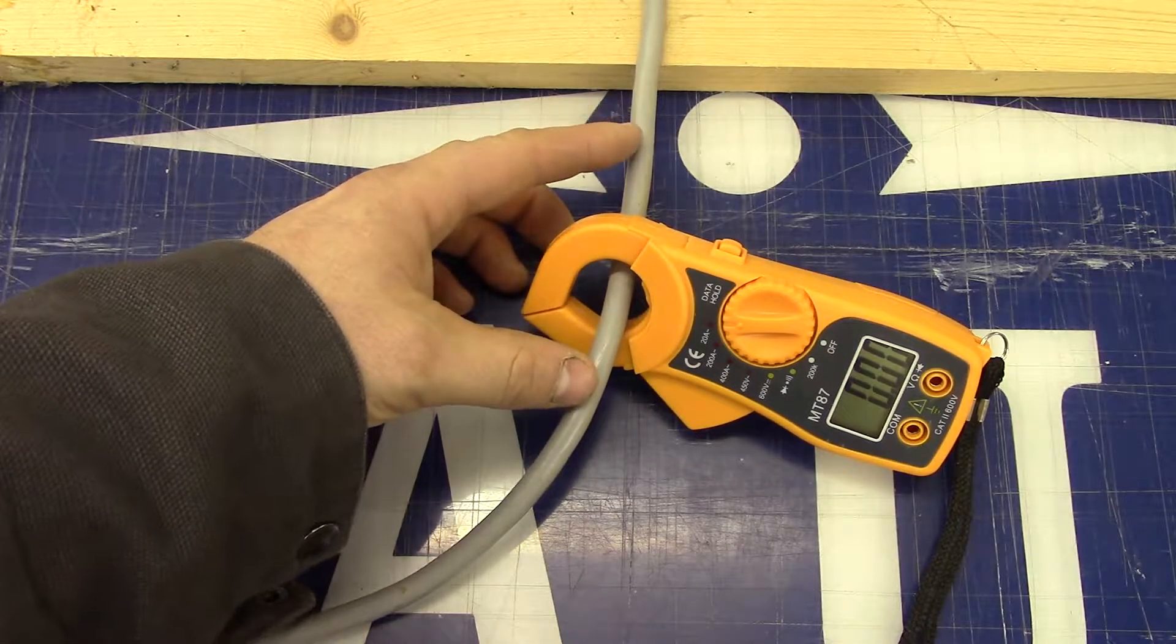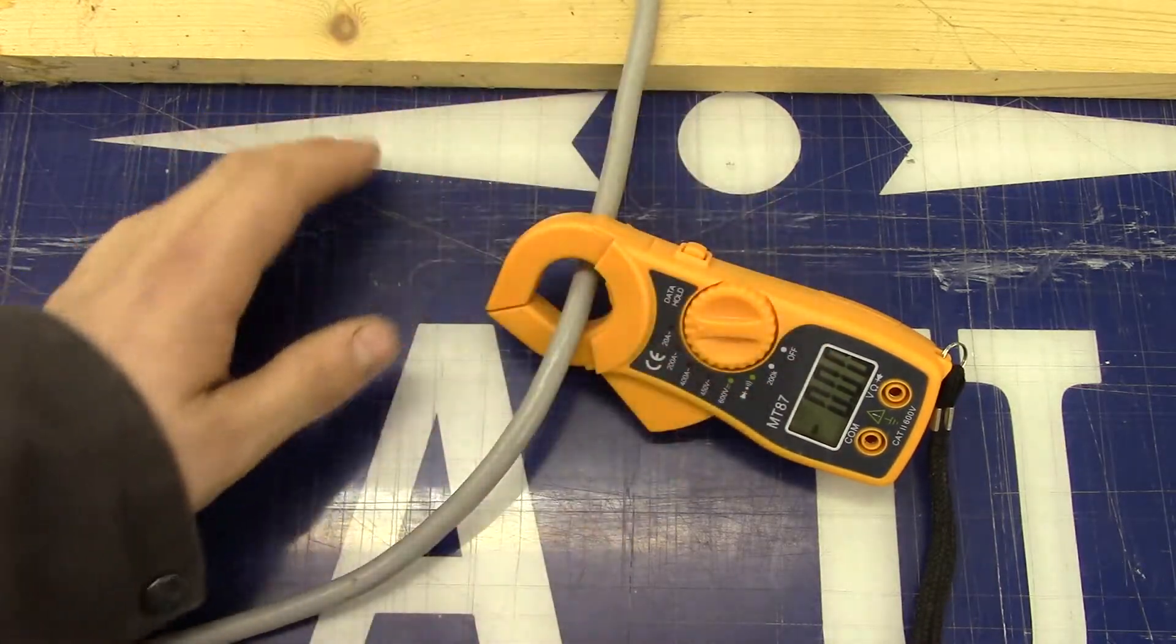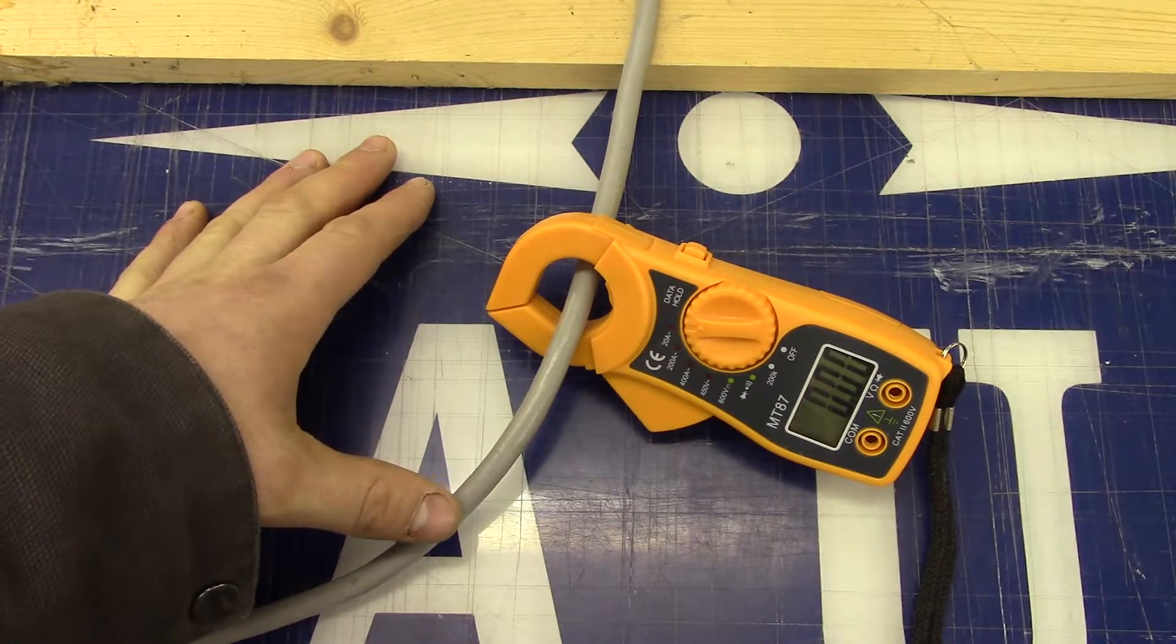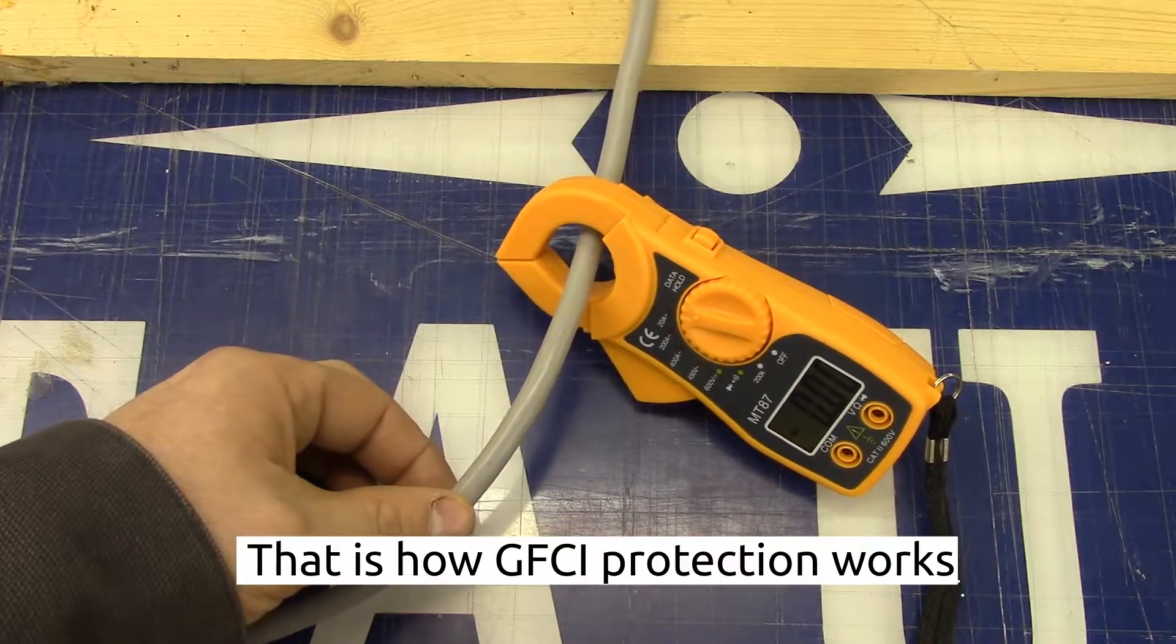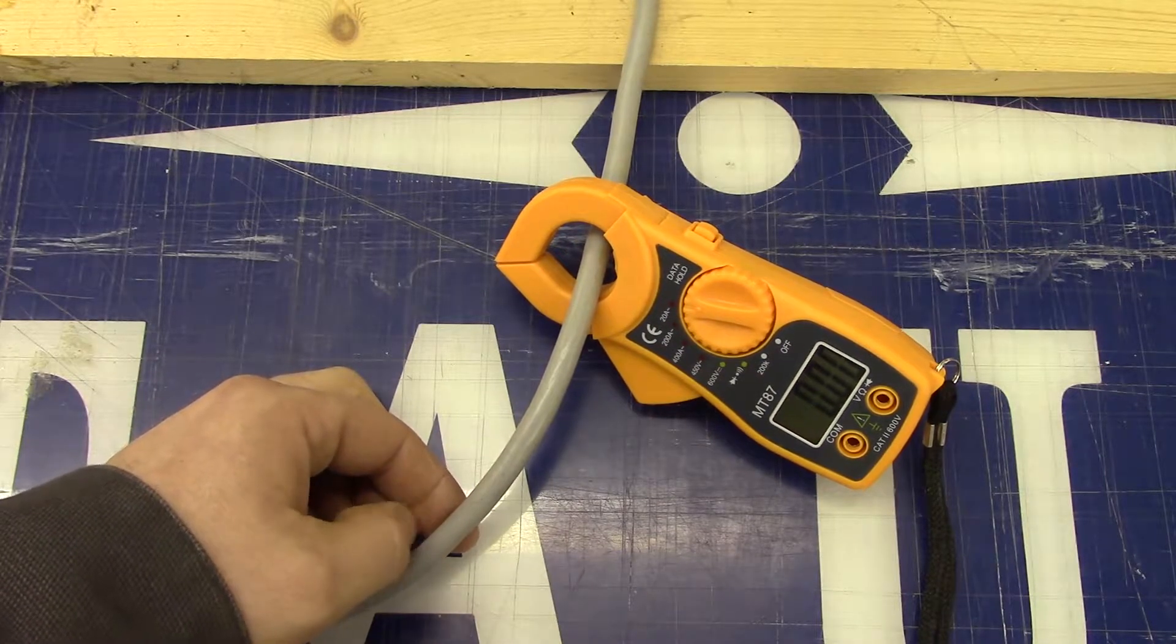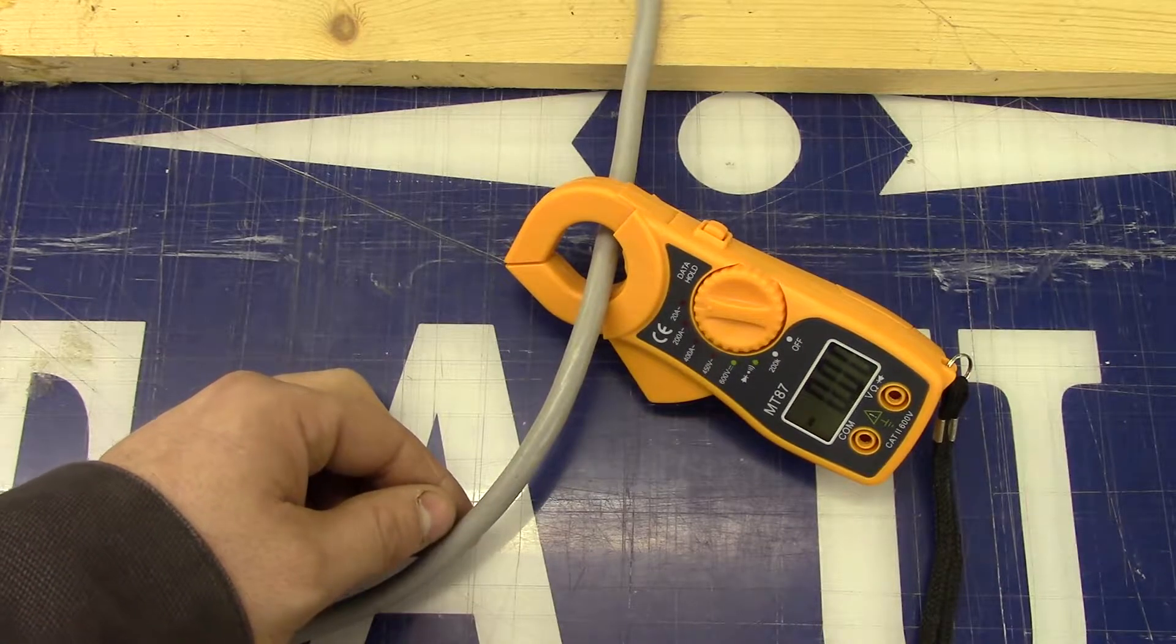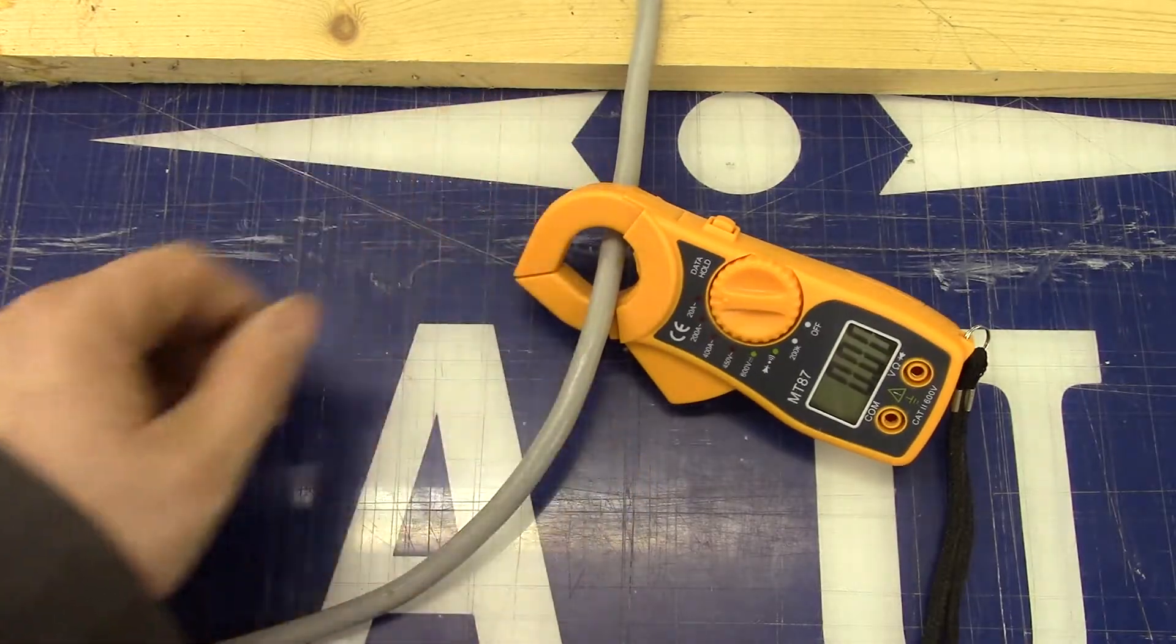And that's what you're going to wind up reading instead of the current flowing, is you're going to wind up with the difference between the two, which should be zero unless you have a short somewhere going to ground, which will actually have the ground wire in here too. So unless you have it shorting going off somewhere else with an alternate path to ground, you're not going to read anything.